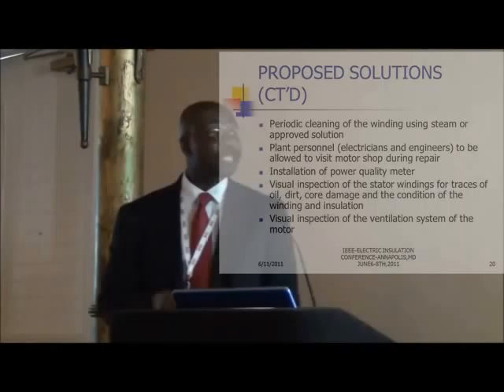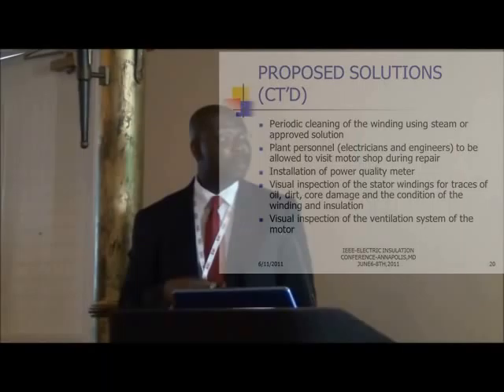Another PM was developed for visual inspection of the ventilation system and the condition of winding insulation, looking for traces of oil, dirt, and core damage when the motors come offline.